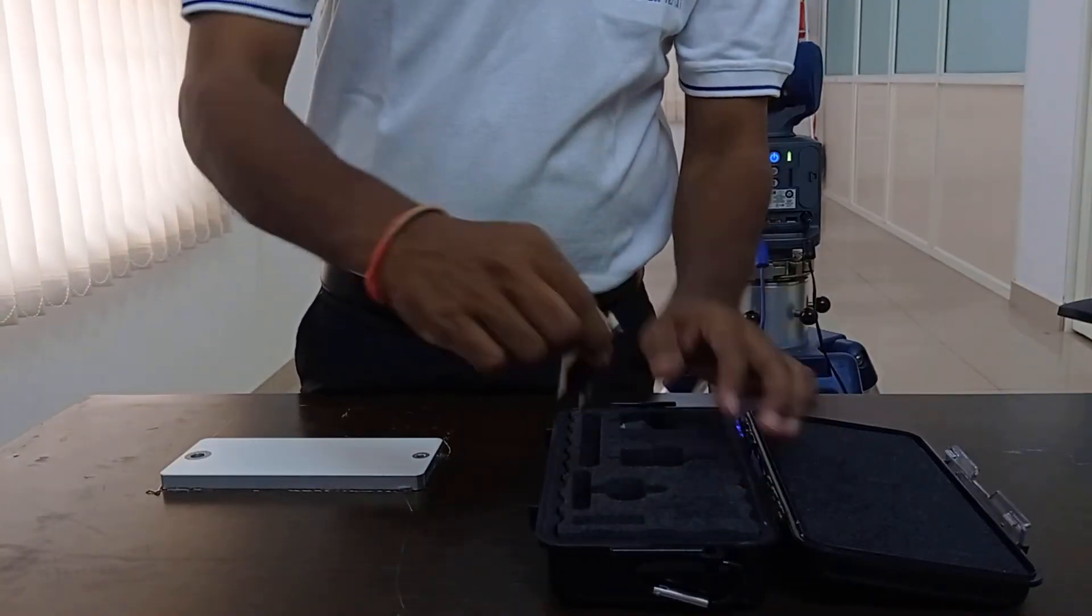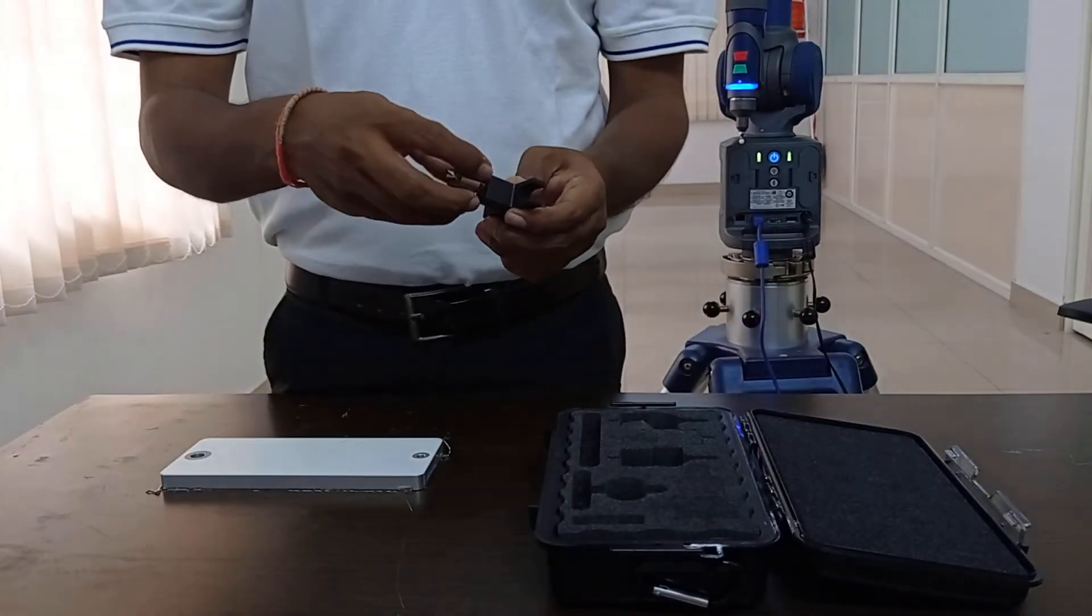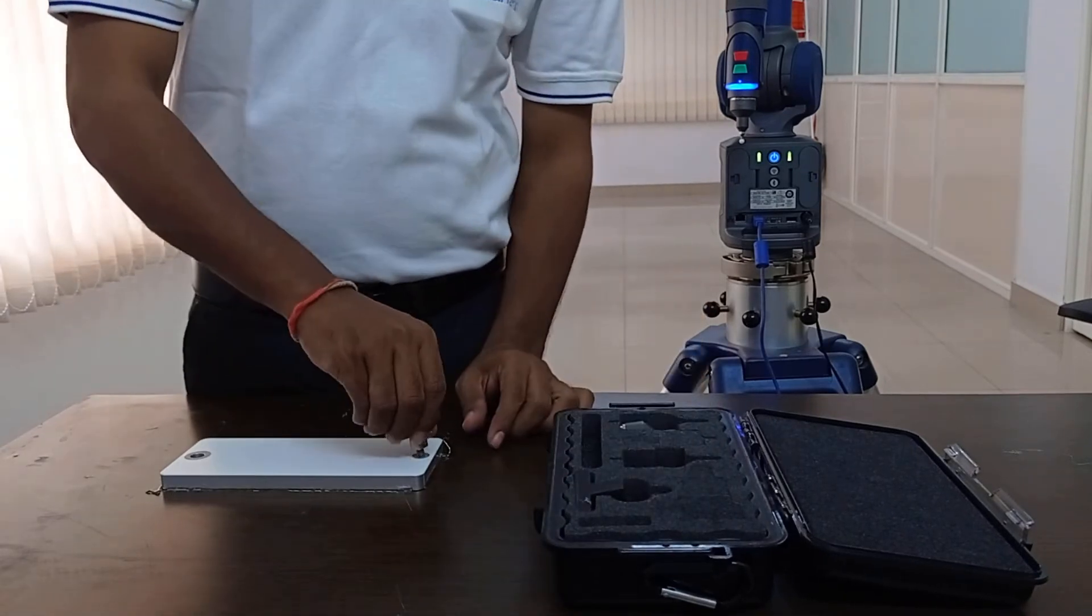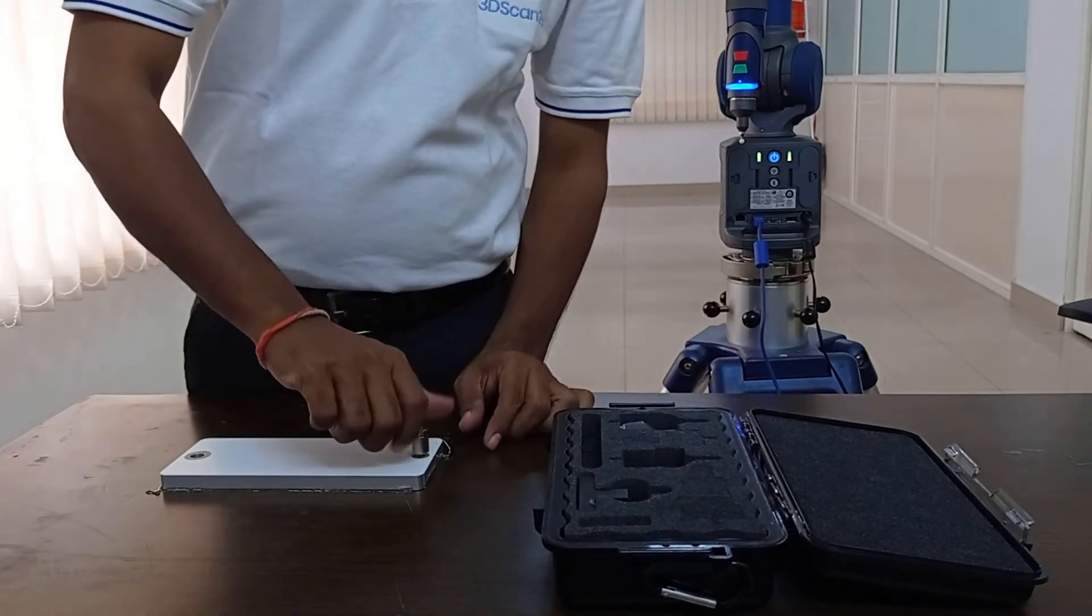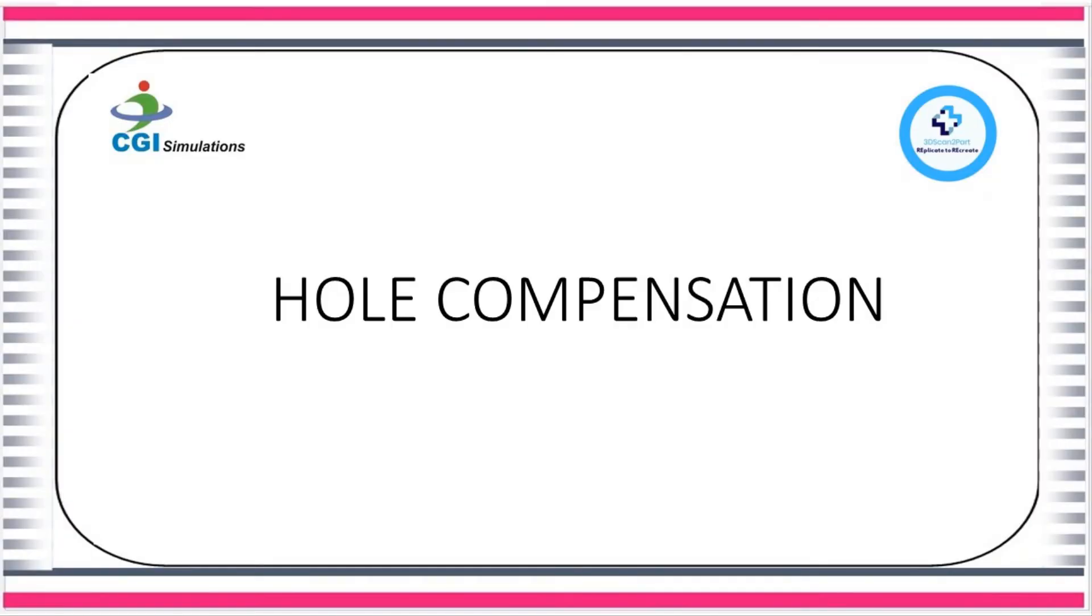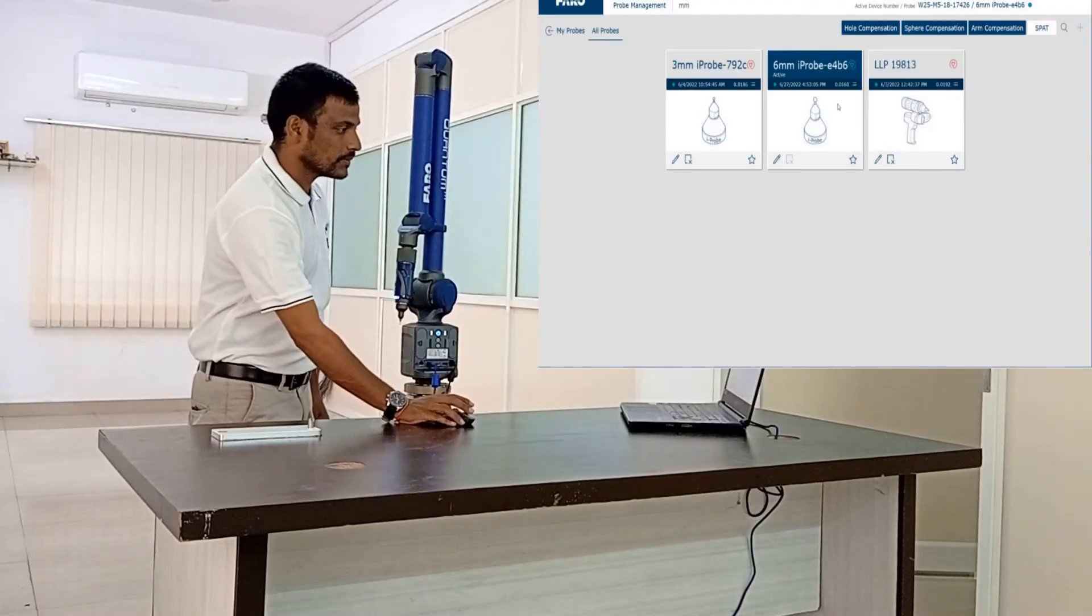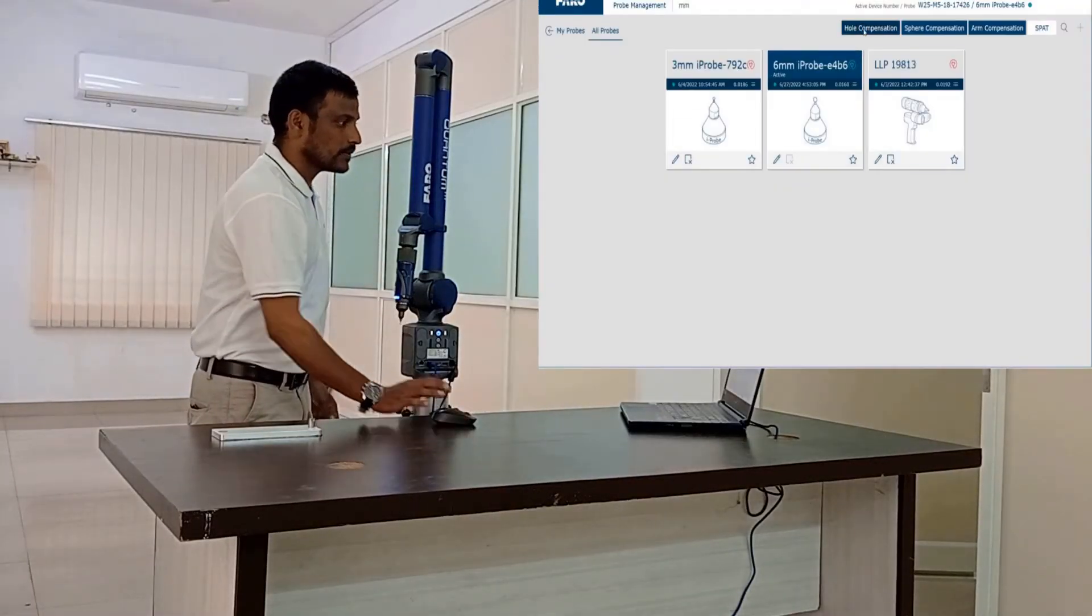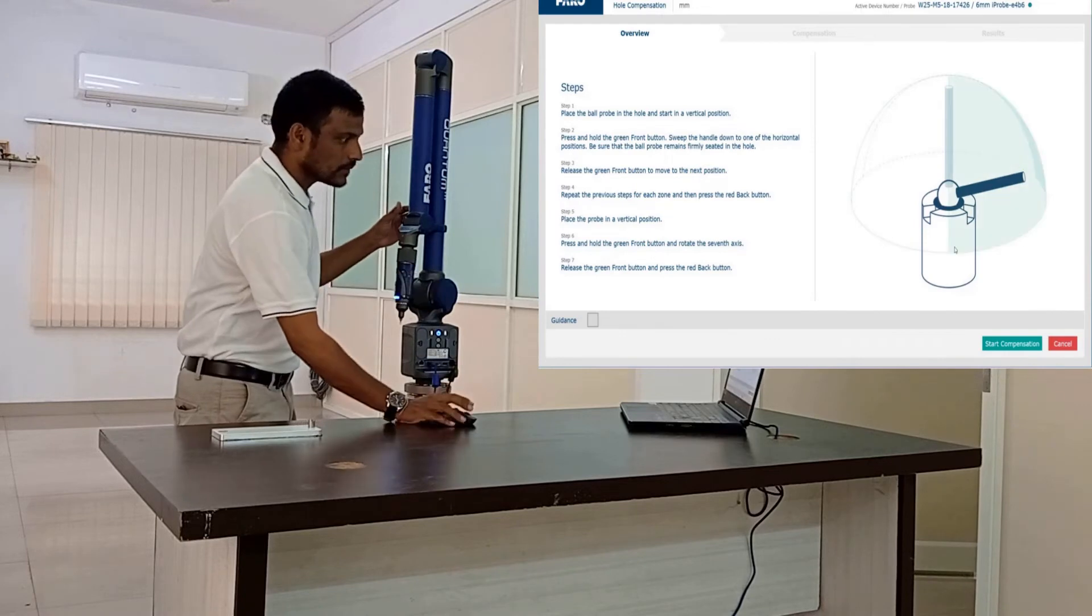Open the compensation cone and screw it to the calibration plate. Let us see how to do hole compensation. Open Faro arm manager and at the top you can click on hole compensation. Using the dialog box that has opened we can calibrate the probe by viewing the instructions.